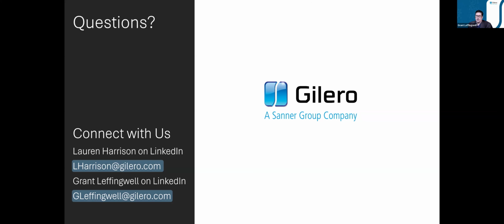We did have someone who asked a question about what the ideal number should be, in your experience, of separate reviewers. Sure, yeah. So I touched on this a little bit in the past slide, but 62366 mentions 3 as your baseline. And then Wickens actually quotes Nielsen, who states 3 to 5. That's kind of your goal for your heuristic, to make sure you're covering all of your bases, you're not leaving any data on the table.